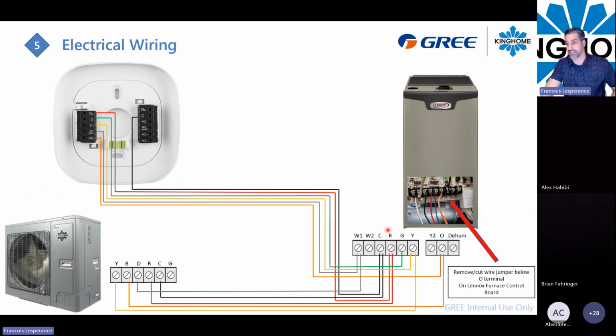Okay, so that's the better way to install it, and all your connections will be inside the furnace at that point. So it's easier to install, and also for you guys, when you do some troubleshooting on the unit, you will know exactly where your connections are, where all your stuff is. So you don't have to connect a wire directly from the outdoor unit to the thermostat. Everything will go inside the furnace cabinet at that point.